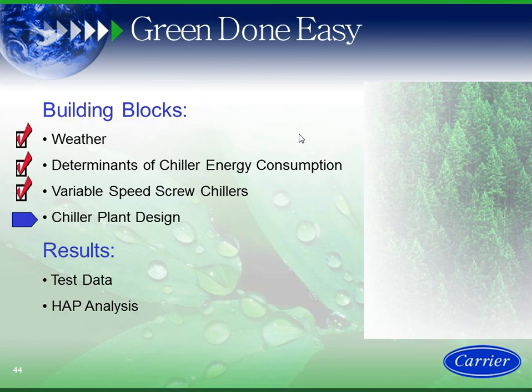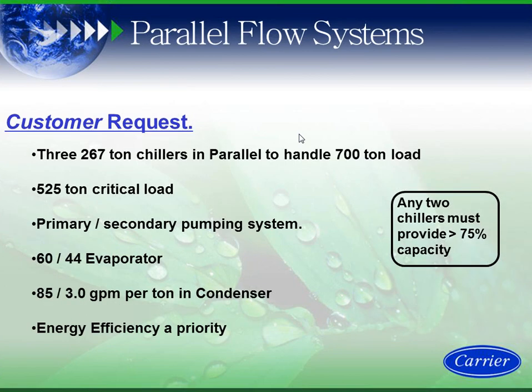Now I'm going to go into a specific problem and show you the energy results here. So we had a customer request for 3 267-ton chillers in parallel to handle 700 tons of load. Okay, why did they want three 267-ton machines? Because at any point, the owner said, I need to have 525 tons of critical load required for the building itself. Okay, so I needed 525 tons of critical load.